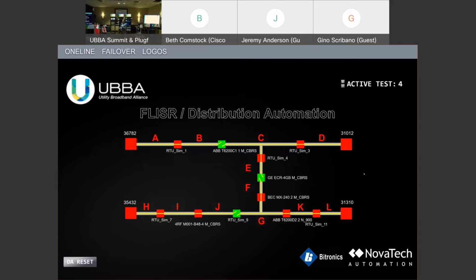other, what might happen here, if I had an example, let's say we're looking at the time overcurrent value of bus J. We have the normally open J, and then we have I and H. If the recloser between J and I was set slower than the one between I and H, we could have a situation where the IH recloser operates before the IJ recloser does. And at that point, we would not have good selectivity. We operated the wrong function of the grid. We cut off more customers than we actually needed to. We actually had an overcurrent device that was closer.